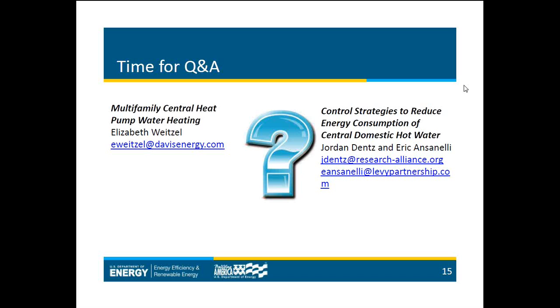Okay. Was there an increase or decrease in tenant satisfaction with demand control? So, like we said towards the end of the presentation, there weren't any formal complaints. We also surveyed the tenants, in addition to periodically checking with the superintendents. And what we found was there weren't any complaints attributed to the demand control, but some people didn't really like that the hot water temperature fluctuated throughout the course of the day. We didn't call that a hard complaint, but it seemed to reduce satisfaction somewhat, the temperature modulation specifically. I don't think demand control yielded any dissatisfaction.